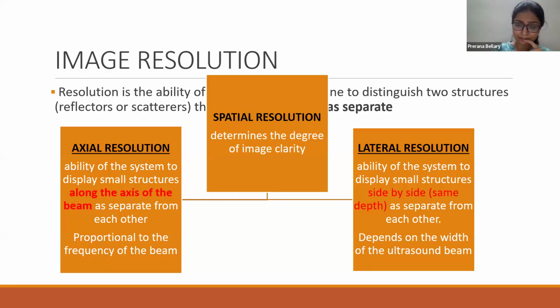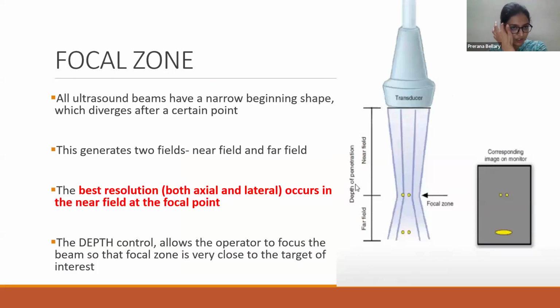Whereas lateral resolution is the ability of the system to display small structures side by side in the same plane at the same depth as separate from each other, and this depends on the width of the ultrasound beam. So when we talk about resolution, there's a concept called focal zone, where all the ultrasound beams have a narrow beginning shape, and then after a certain point, it diverges. So at this point where it diverges, two fields are created, that is a near field and a far field, and the point where it converges is called the focal zone. So it is at this focal zone that the best resolution takes place, both axial and lateral.